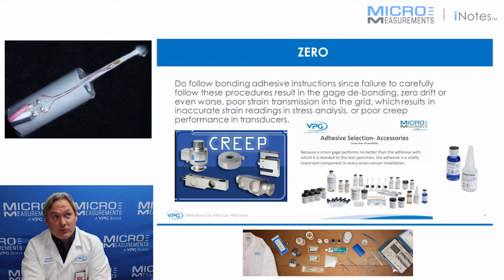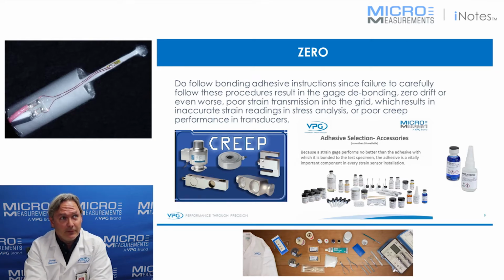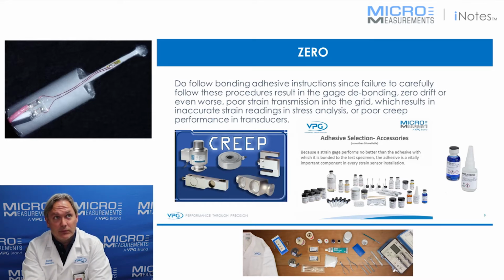Do follow the bonding adhesive instructions, since failure to carefully follow these procedures can oftentimes result in a gauge debonding, or maybe a zero shift or drift, or even poor strain transmission into the grid, which can result in inaccurate strain readings for stress analysis or poor creep performance in transducers. Zero return is one of the most important characteristics to monitor when you're trying to evaluate an installed strain gauge. And oftentimes poor zero return is created by not properly installing the strain gauge. It could be that the adhesive was out of date. It could be that maybe the instructions weren't followed precisely for how to install it.